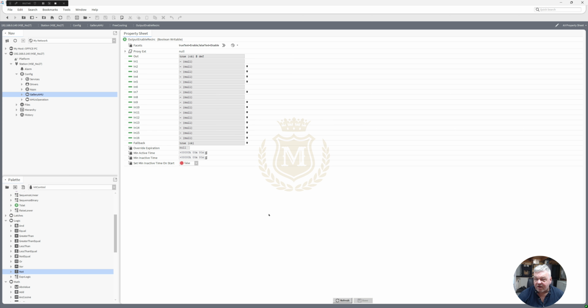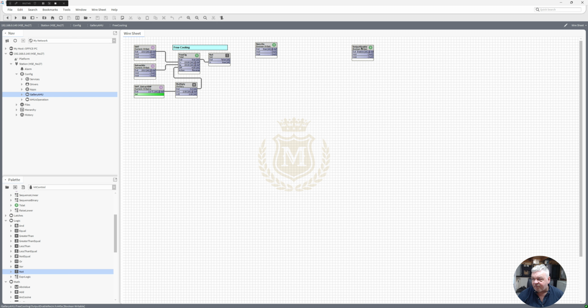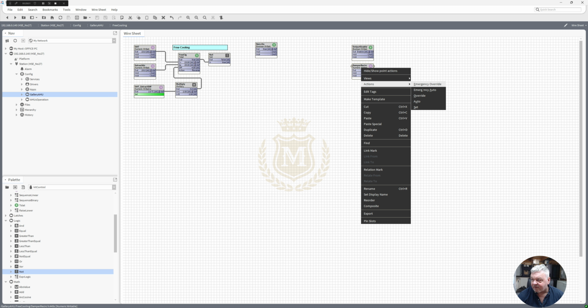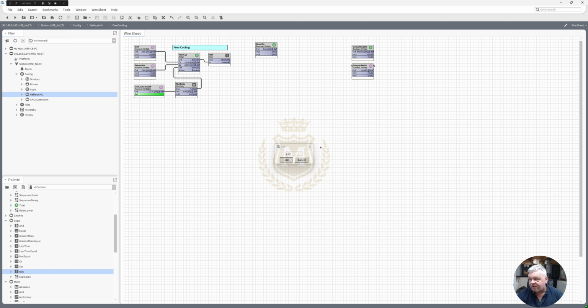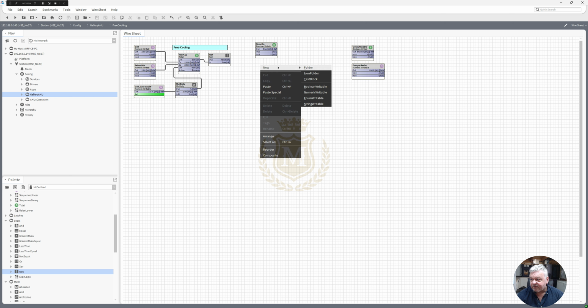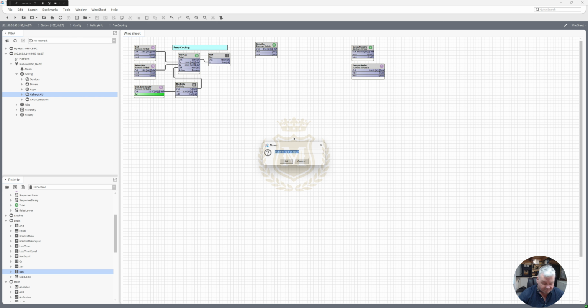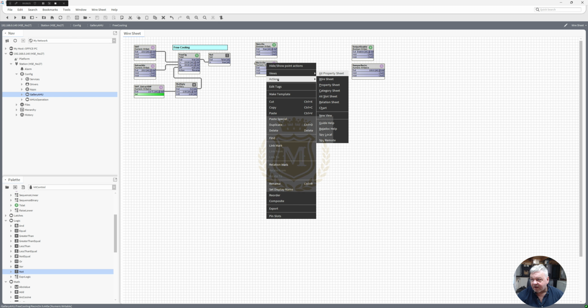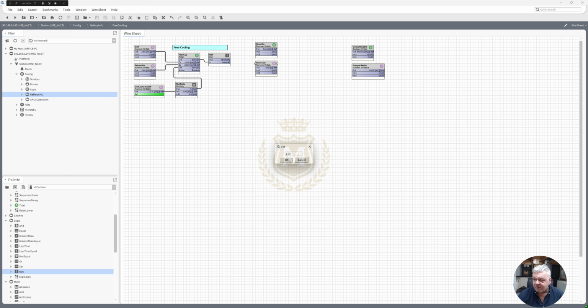Or it may be that you're using a 0 to 100% on a valve. So let's just go new, numeric writable, damper recirc. And it could be that that damper is set to 100%. And then you've got some logic here that's telling it 100%. So numeric writable and recirc on 100%. Action set 100%. So you've got some logic, other logic that's saying that we want the recirc on, and that's going to go to there, or it's just an on and an off, and that's going to go to there.